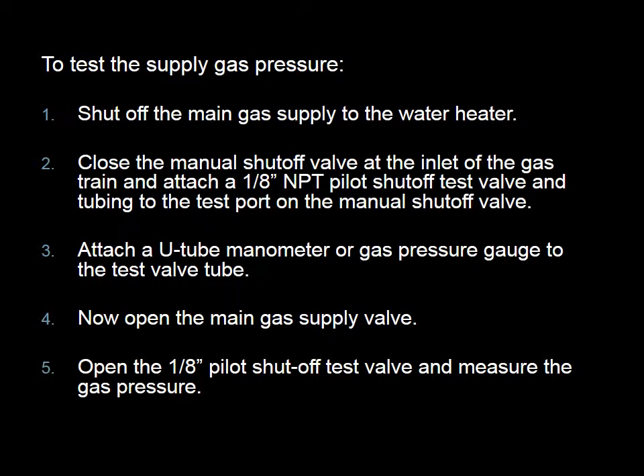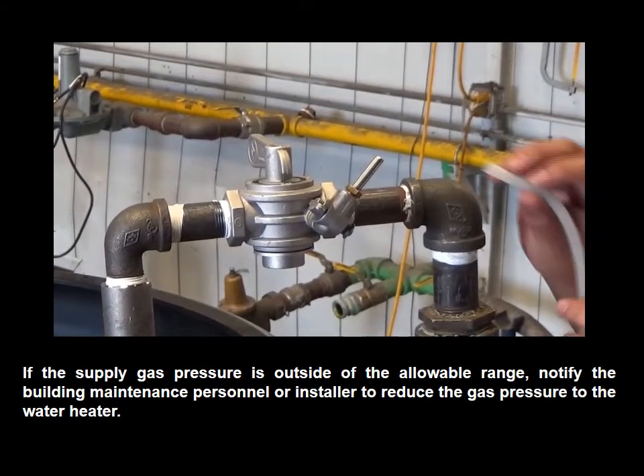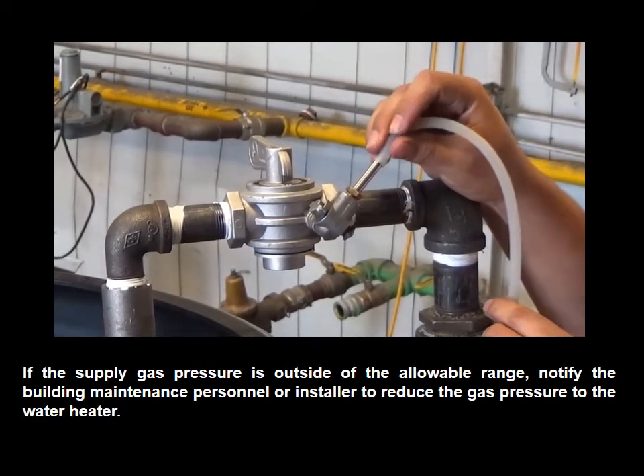To test the supply pressure, first shut off the main gas supply to the water heater. Then close the manual shutoff valve at the inlet of the gas train and attach a 1/8 inch NPT pilot shutoff test valve and tubing to the test port on the manual shutoff valve. Attach a U-tube manometer or gas pressure gauge to the test valve tube. Now open the main gas supply valve. You're now ready to measure the gas pressure supplied to the burner.